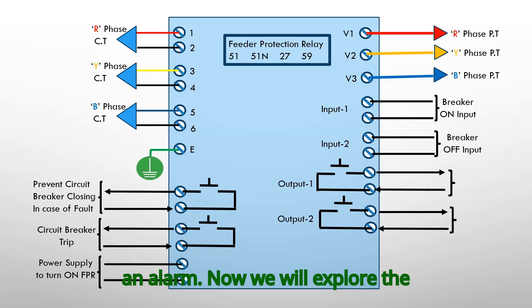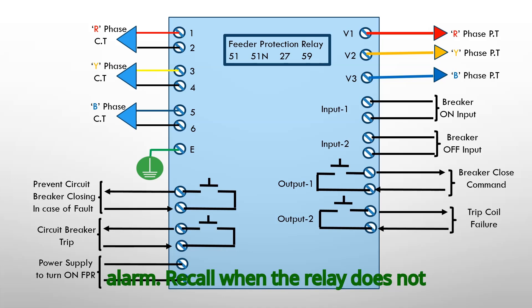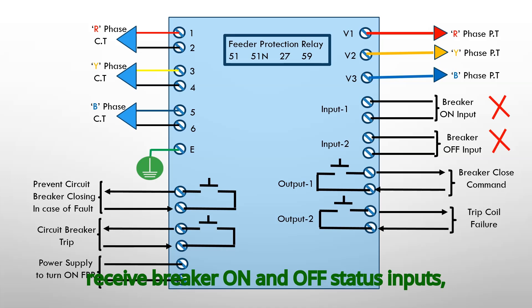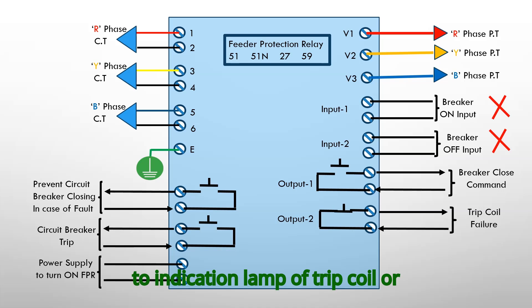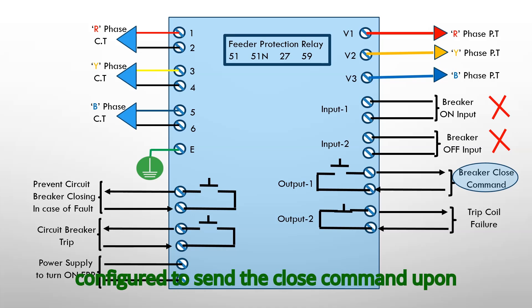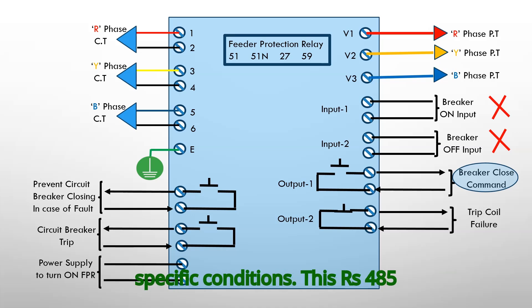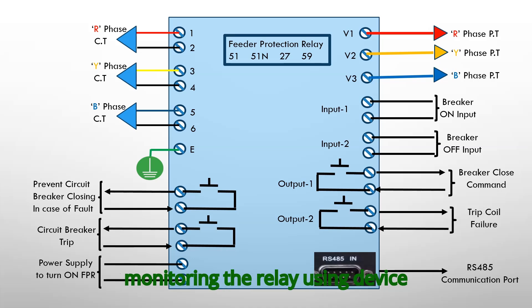Now we will explore the configured outputs: breaker close command and trip coil failure alarm. When the relay does not receive breaker on and off status inputs, it sends a trip signal from this output to the trip coil failure indication lamp. The breaker close command is built-in and programmable, configured to send the close command upon specific conditions. This RS-485 port enables connecting to a PC or laptop for configuration and monitoring the relay using device software.